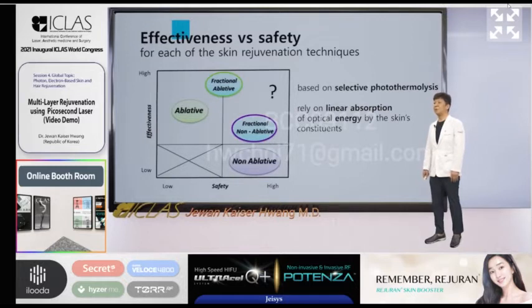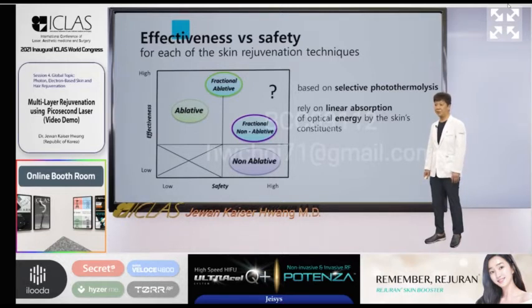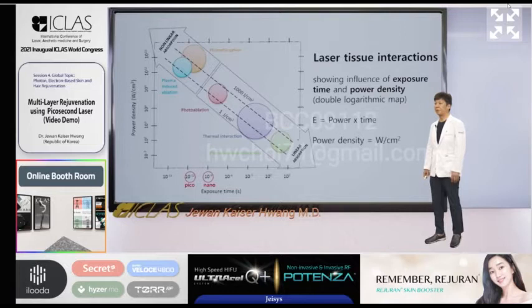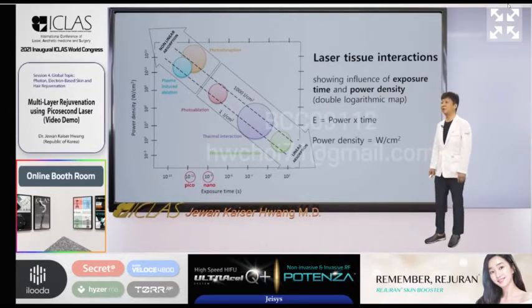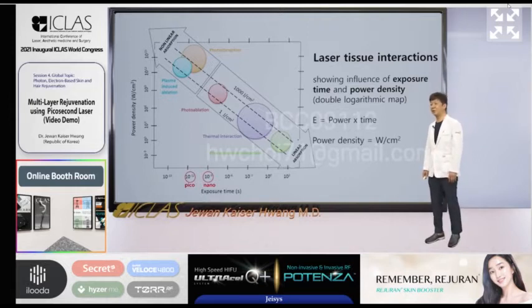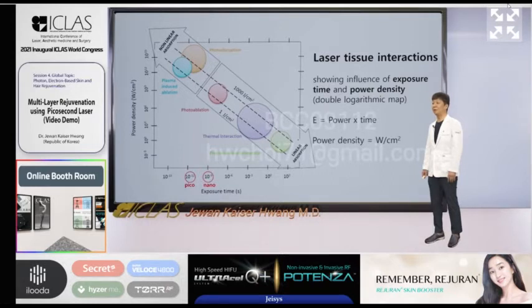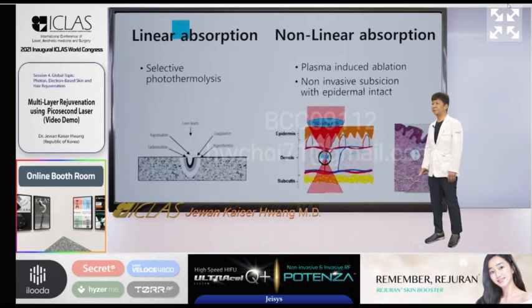These modes of operation are not a matter of which is absolutely good or bad, but which is more important between effectiveness and safety. This laser-tissue interaction occurs due to the relationship between pulse duration and power density. In nanosecond or picosecond laser, plasma-induced ablation or photo-disruption may occur due to non-linear absorption at high power density. Linear absorption is the domain of selective photothermolysis, and non-linear absorption is the domain of LIOB or LITB.